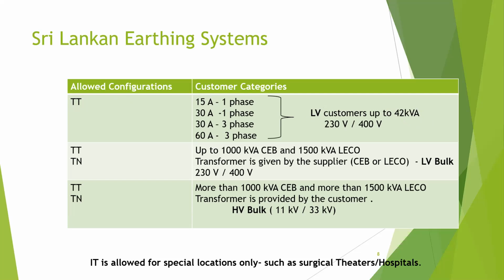If you know about the meter panel in your home, there will be a breaker or a cutoff. That cutoff is rated for some value. Usually 30 ampere connections will have a cutoff of 40 ampere. So go and check those things out and define what customer category you are in. Usually for three phase we have 30 ampere, three phase 60 ampere. So these are the LV customers. LV customers can only have the TT earthing system.